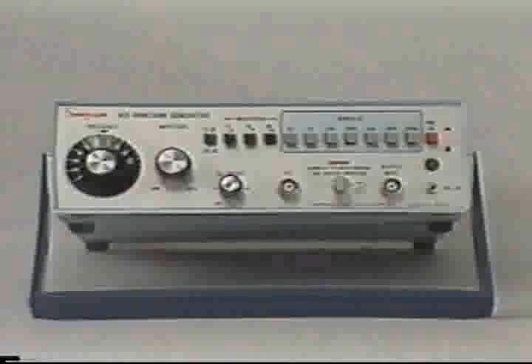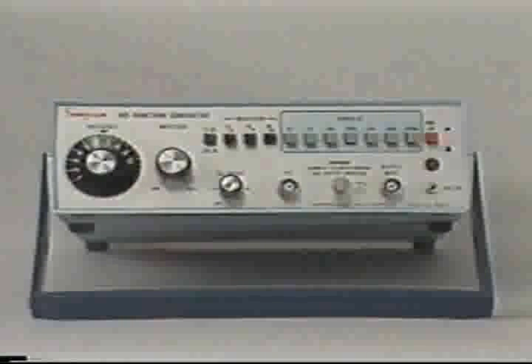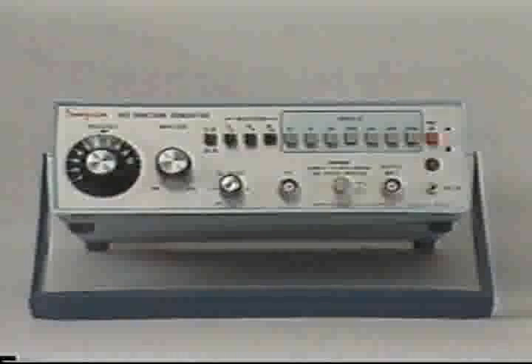These pulses are conditioned and sent to the transmitter, which then sends an appropriate output to the next instrument in the loop. In order to calibrate this transmitter, we need an input standard which can simulate the electrical pulses counted by the transmitter. This is the calibration setup for a vortex shedding flow meter. A frequency generator is the input standard for this transmitter. The frequency generator has some functional features you'll need to see before you can calibrate the transmitter.